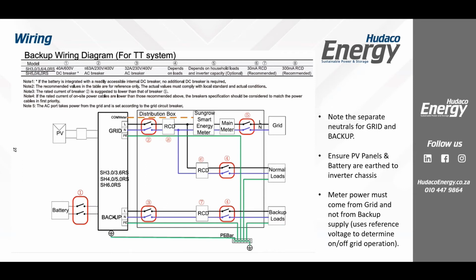And then the third thing, please make sure that there's no loads, which we've spoken about between here, because it uses the reference voltage. Oh, sorry. This is not about no loads on the right. This is about where we get the power for this. Okay. Take the power to this, please, from the grid supply side. When we did our first few installations, we thought, oh, it's a great idea. So when you put the power here, please take the power here from this supply line. In other words, from the grid supply line or the grid breakers, right?